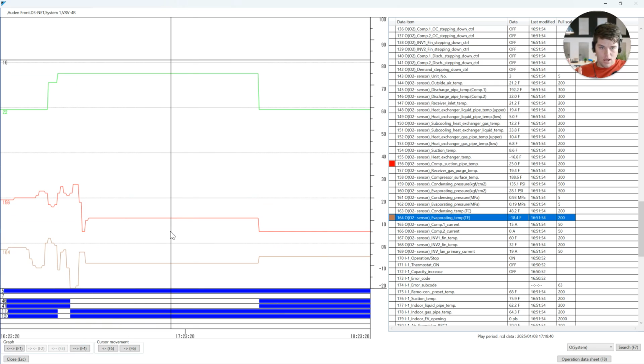All right, we're going to go back to the very beginning of the data set. Okay, and here we are. What is my suction superheat? Anybody? Oh, like I'm in a crowd here. We've got 23 degrees compressor suction pipe temp and negative 18. We can pretty much just add the 18 on top of the actual 23 degrees. What is that number? That number is 41 degrees. I have a 41 degree suction superheat.